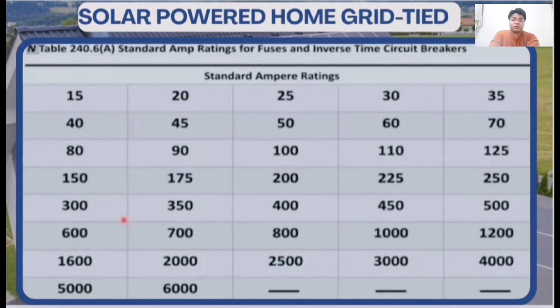Hindi tayo pwede mag-round down kasi kapag mas mababa ang breaker kaysa sa actual load, posible na mag-trip ito kahit normal ang operation. Kaya ang rule ay laging next higher standard rating para masiguradong safe at stable ang system. Sa madaling sabi, ang table ng standard ampere ratings ay mahalaga dahil ito ang ginagamit natin para sa tamang sizing ng fuse at circuit breaker, safety ng electrical installation, reliability ng protection system, at syempre compliance sa electrical code requirements. Kaya kahit may computed value tayo mula sa design, ina-adjust pa rin natin ito sa standard ratings para maging practical, safe at compliant ang final installation.